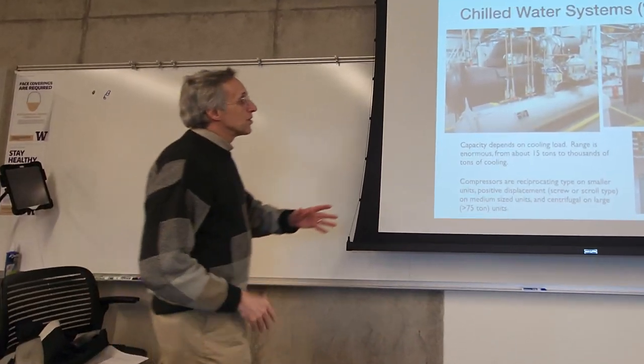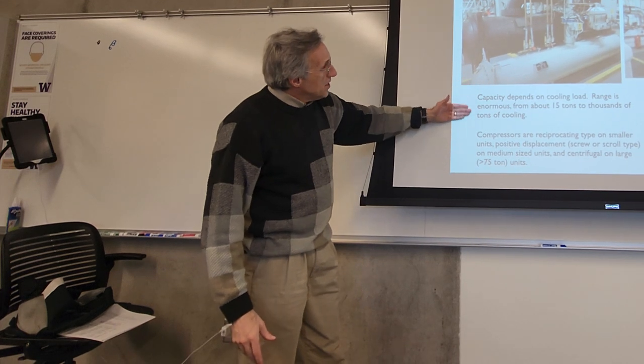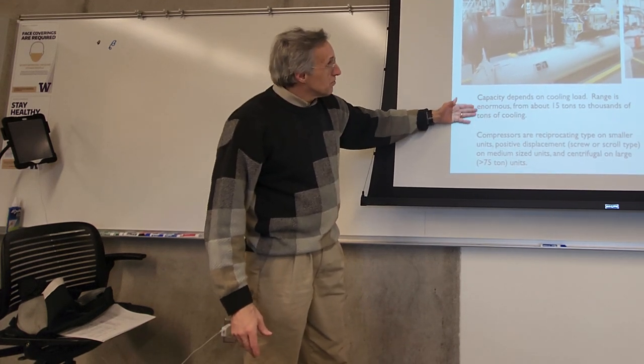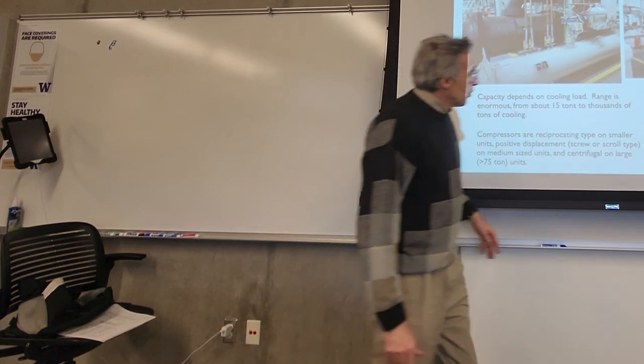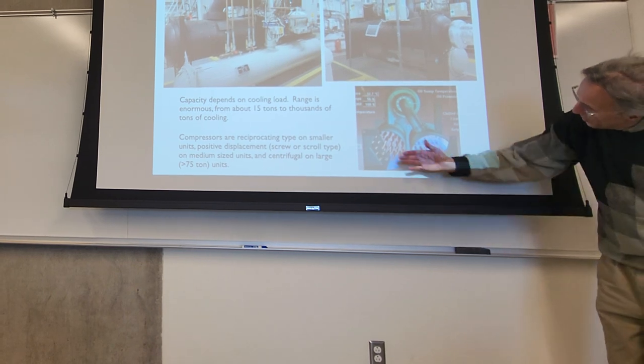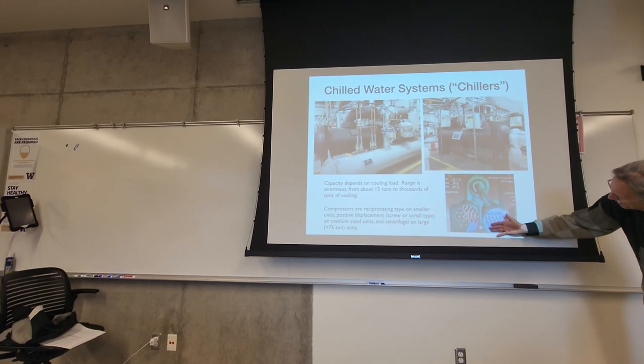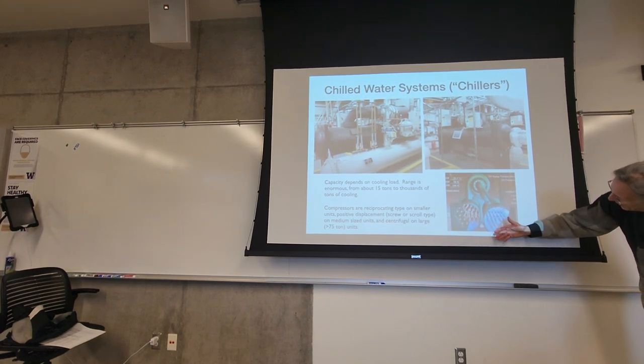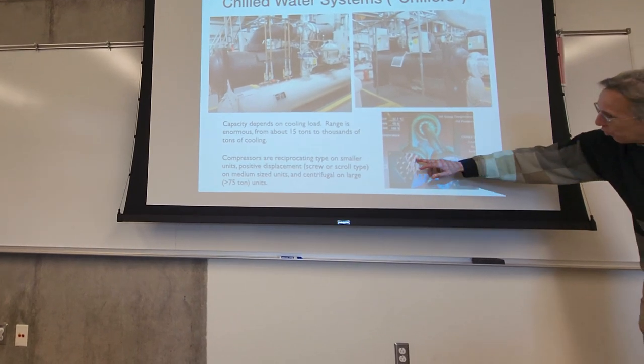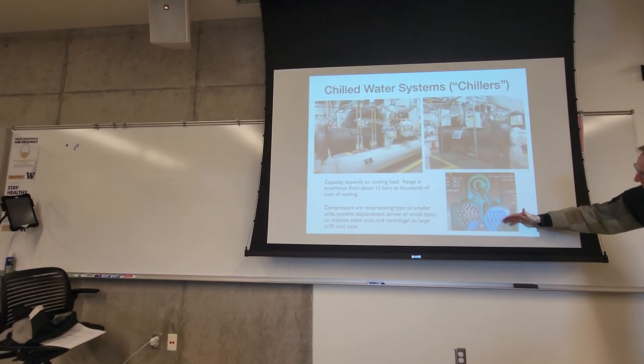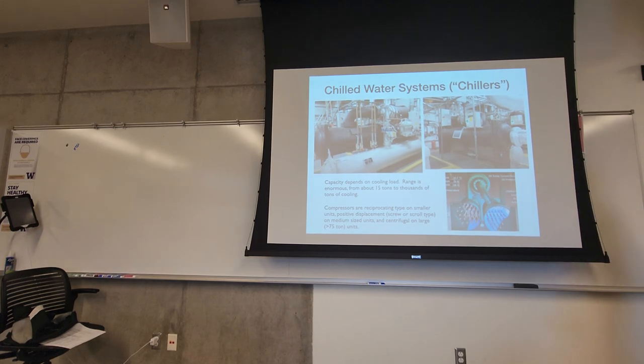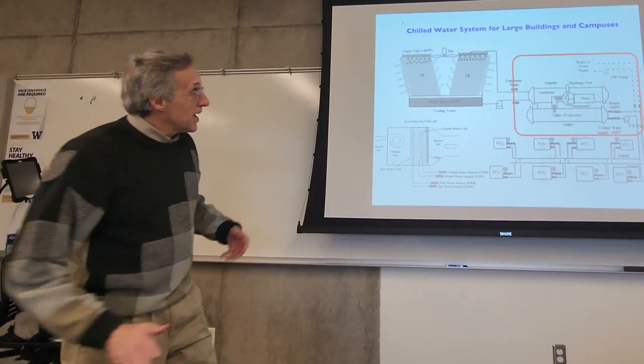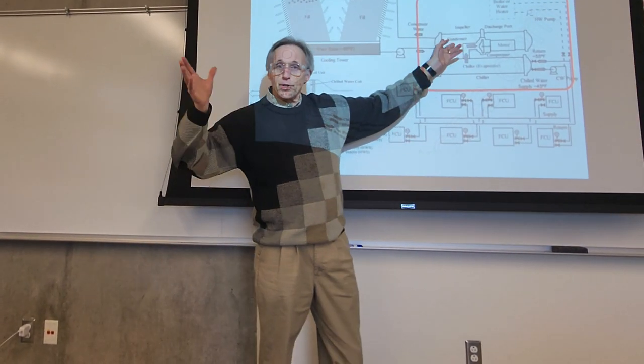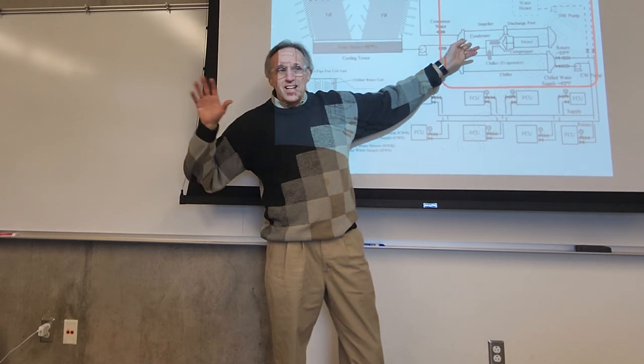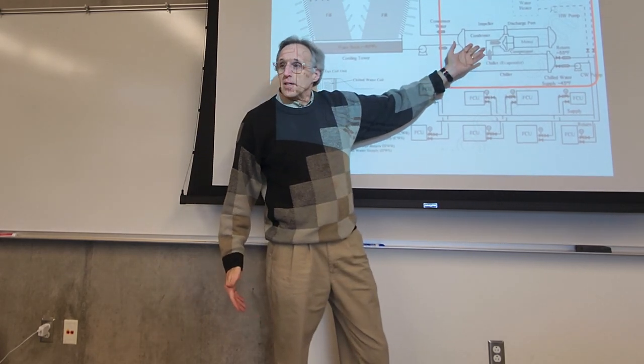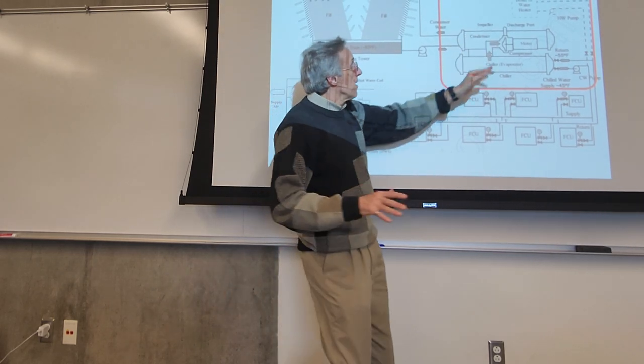And then the chilled water chillers, what these look like, and these can get really, really big, thousands of tons of cooling. And if you were able to cut open the condenser or the evaporator, this is what they would look like. You'd see them filled with water and refrigerant flowing through those many, many pipes, again, maximizing surface area of contact between cold refrigerant and water, or in the condenser between the hot refrigerant and the cooling water. Because the other thing about these systems is that with the condensers, you no longer can just have a little fan blowing air over the condenser. You need really intense cooling going on here to draw the heat.